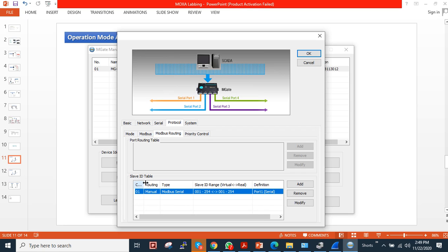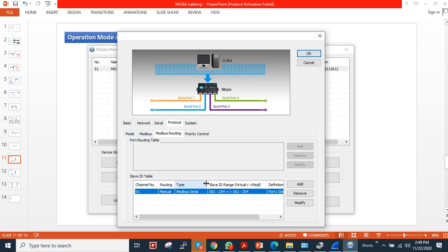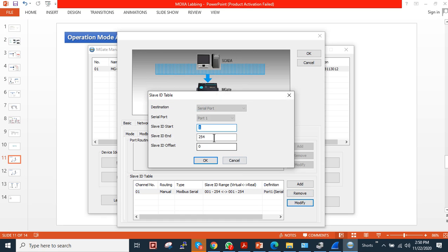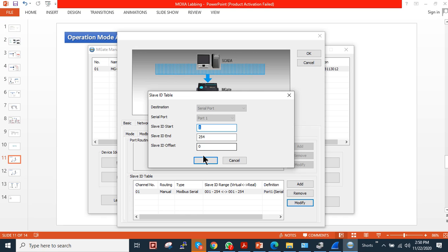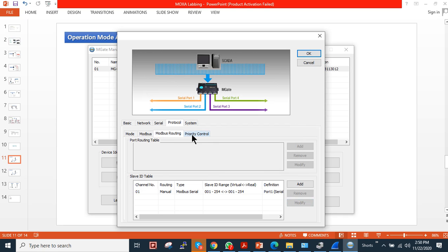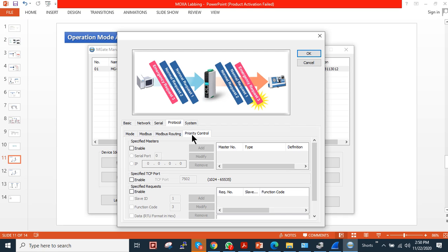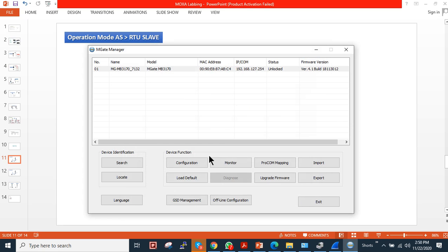The TCP/IP port is 502 default. I will keep the default port. For Modbus routing, if you want to change the slave ID values, you can change them here. As you can see, it's showing port 1, so you can click modify and change the slave ID values. The default is allowed from 1 to 254. I will keep the default 1. I will click okay. Priority - I don't want to check anything else. I will just click okay and configuration is finished.